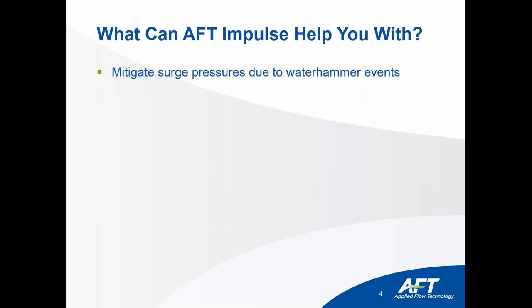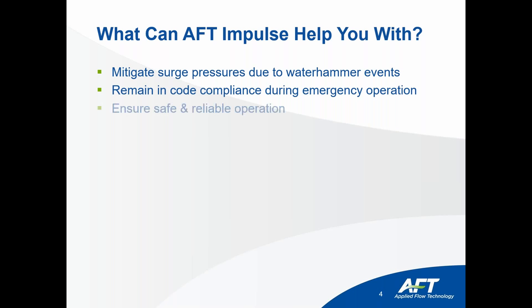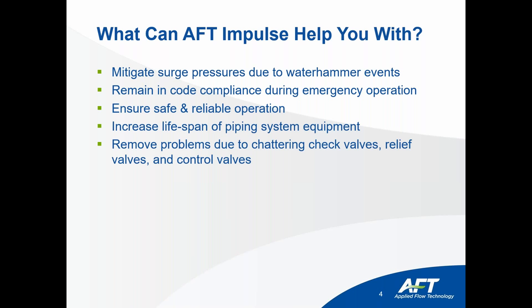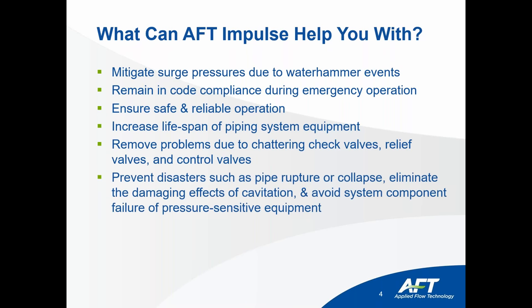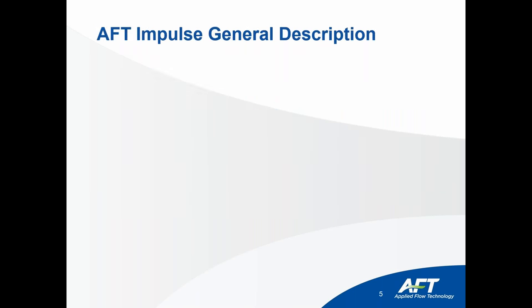You want to make sure that the pressure surges your system experiences do not cause a problem. AFT Impulse will help you identify where the maximum surge pressures will happen and give you guidance on how to implement various surge suppression measures to mitigate those issues. It can also help you maintain code compliance, ensure a safer and reliable system, increase the lifespan of your piping system equipment, remove chattering check valves, relief valves, or control valves, and identify if you've got cavitation happening and what the pressure spikes will be if you have a cavitation collapse.